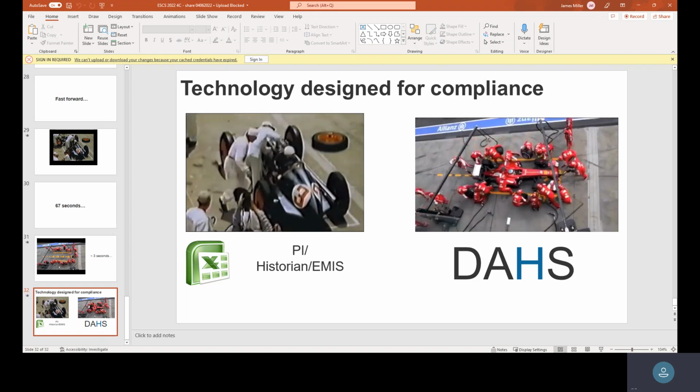There are a lot of different ways to do this. I don't have pictures of it today. We have the ability to go in, and there's a PLC device or a data controller that's tied directly in with the equipment, so it operates independently of the application. It can record and provide values and do calculations, and it marks them based on the status of passing or failing a daily check. Or if there's a fault line coming in from the instrument, it can start flagging the data as that fault line is, the digital is closed.